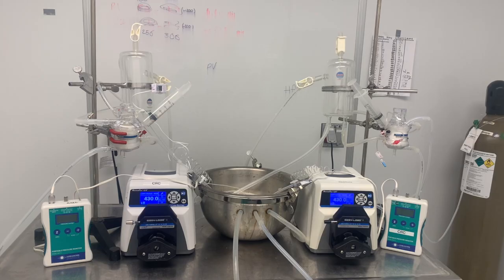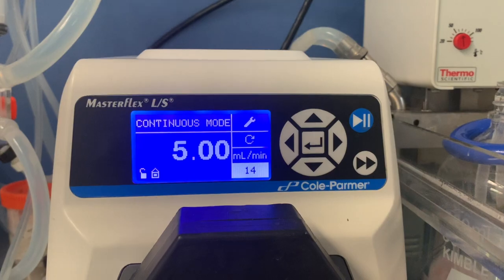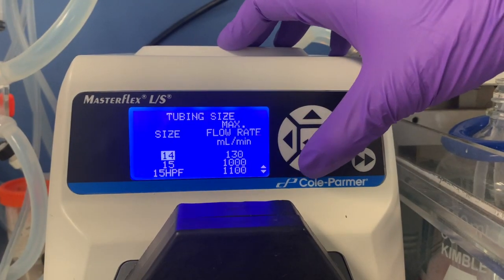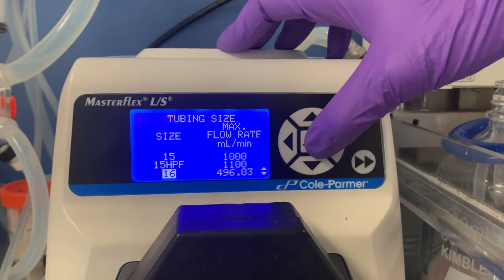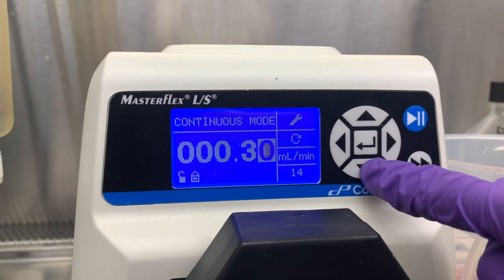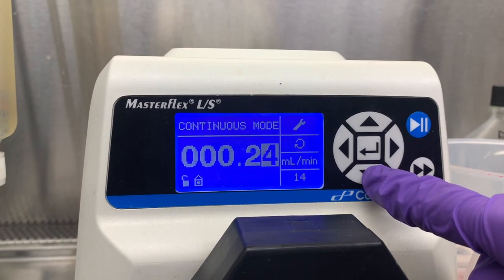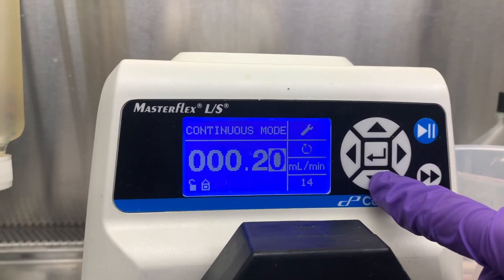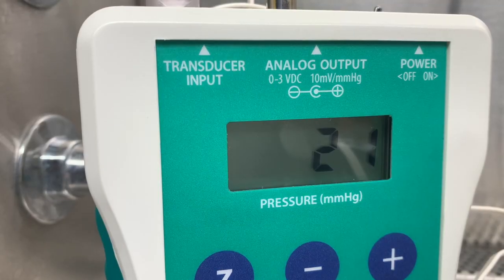Tubing comes in a large set of gauge sizes. For example, we would use a large tube for human liver to accommodate for higher fluid mass transfer. Our pump is compatible with a range of tubing sizes, which we change accordingly. The flow rate can be precisely controlled to affect the pressure. Decreasing flow rate can work to decrease pressure within the organ.